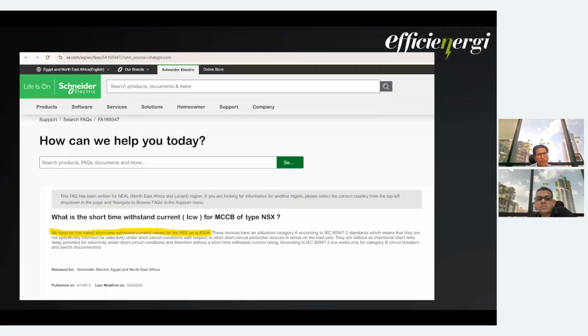So we have taken a screenshot from the Schneider website to explain to you to what extent ECPL goes to check the documentation. Here on the Schneider website, they have clearly mentioned that there is no ICW value for NSX up to 630 ampere. So up to 630 ampere, all these breakers have to trip on instantaneous. These devices have a utilization that is a different category. We normally go for category B, where we have to disable the instantaneous. So at this level, we have to check the conditions at the site before we submit the TCC.